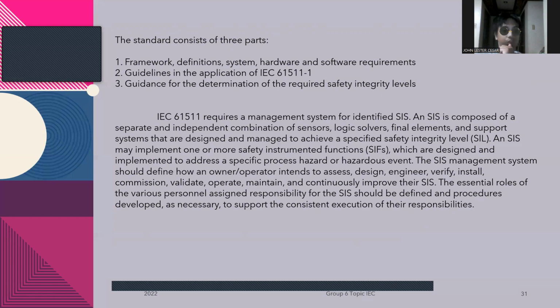IEC 61511 requires a management system for identified SIS. An SIS is composed of a separate and independent combination of sensors, logic solvers, final elements, and support systems that are designed and managed to achieve a specified safety integrity level.